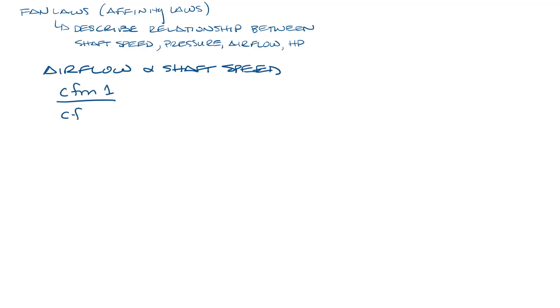The equation is CFM1 over CFM2 equals RPM1 over RPM2. So let's say we have a fan that's running 2000 CFM at 1100 RPM. How much airflow would we get at 2000 RPM?